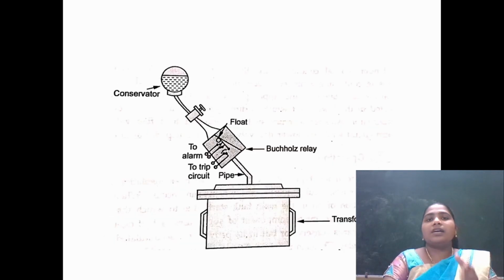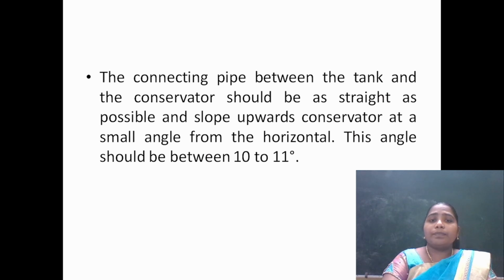So this is the construction diagram of a Buchholz relay, and here the Buchholz relay is connected. This is a Buchholz relay. Here this Buchholz relay is connected in a pipe between the conservator and the transformer tank, so that the pipe between the tank and the conservator should be as straight as possible and slope towards the conservator with a small angle of 10 to 11 degrees.